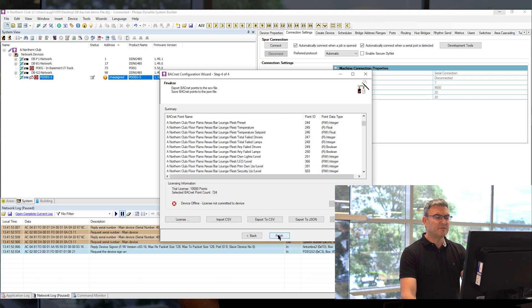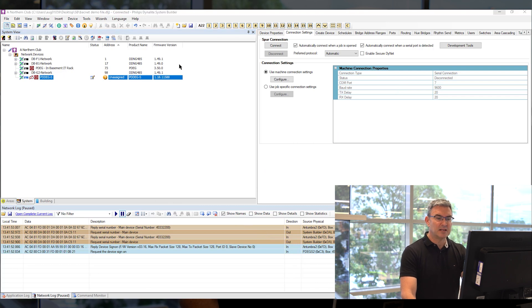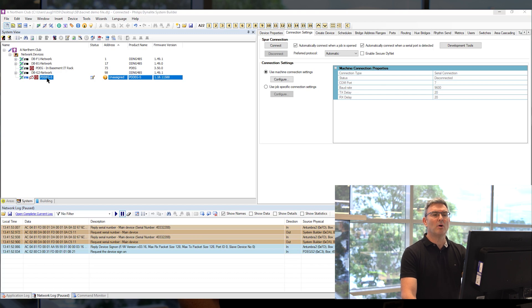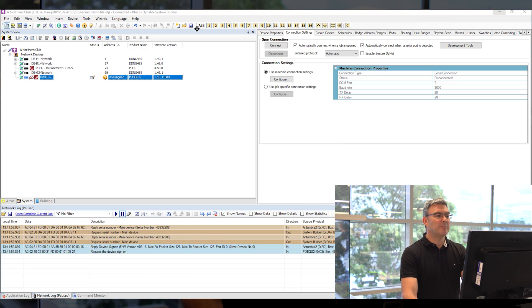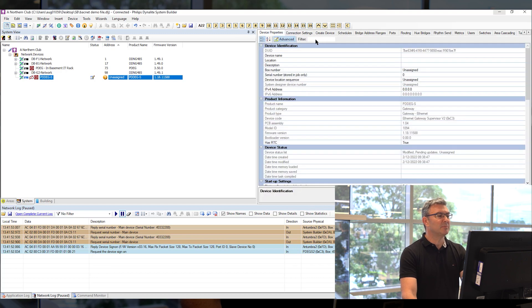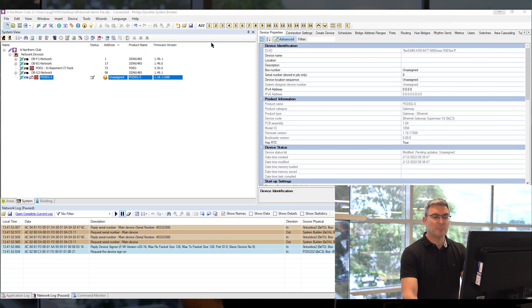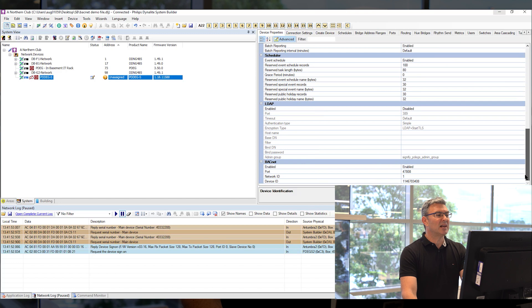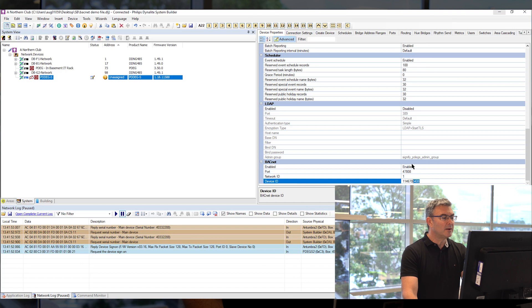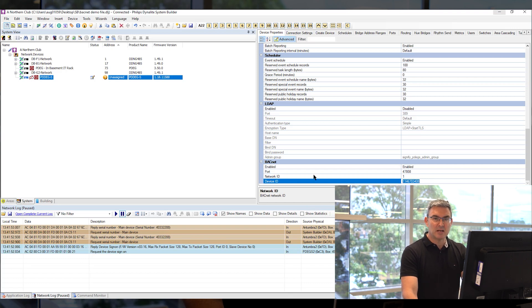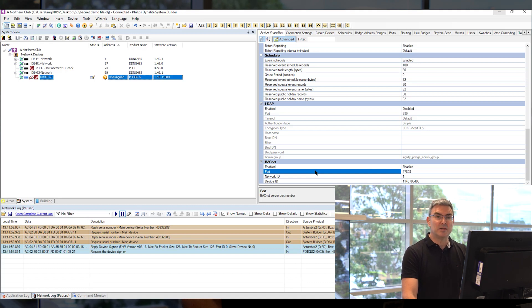When you're done you say finish your system is now operational you can now test it. You will need to give the BMS integrator one more collection of information and that is they may need the IP address of the device which is available in device properties and if you scroll down to the bottom of device properties we have this BACnet section if you click advanced you can see the network ID the device ID the port number and you can share that with the BMS integrator and that will allow him to get his BMS clients to connect to our BMS server.